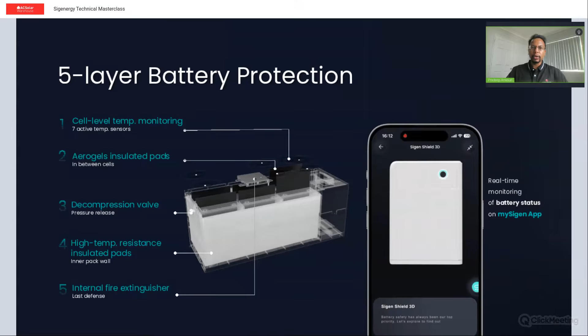That goes off at around 170 degrees centigrade, and then that will isolate that battery pack. The rest of the batteries all have individual DC-DC optimizers, so they can still function. And if you've got multiple stacks in a commercial scenario, you've got a lot of redundancy built in. And there's real-time monitoring, which the customer can access, installers can access. They can see the temperature, they can see which cell is being used up to that granularity.